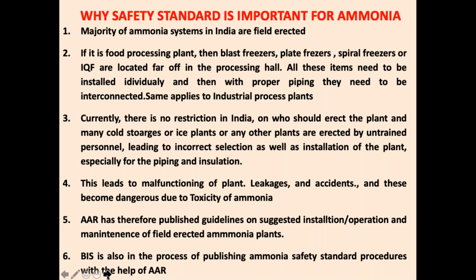Currently, there is no restriction in India as to who should construct a cold storage or ice plant or any other plant, or who should erect it, leading to incorrect selection as well as incorrect installation, especially as far as the piping and insulation are concerned. We take a lot of care in selecting the proper equipment like compressors, condensers, receivers, or motors. But when it comes to erection, people try to give it to someone who is known to them and who doesn't have much expertise on ammonia plants. And this is one of the major reasons why accidents or malfunctioning of the plant take place. This leads to malfunctioning of the plant, leakages and accidents.